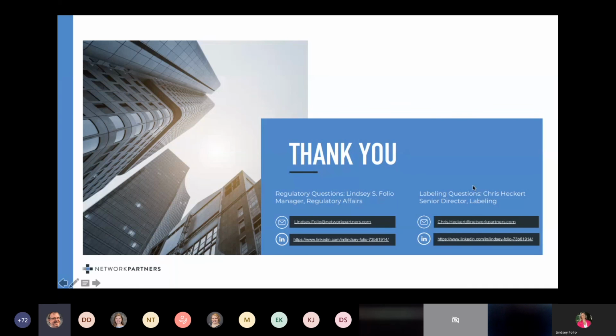You're probably going to have that symbols glossary in your IFU anyway, unless you're using all harmonized symbology. So I'm having a hard time with the question because the symbology is for EU. We put it on the label and we have the opportunity to leverage it with the FDA. I would say symbols glossary in your IFU is the way to go. And you're obviously going to have to put the English definition for those symbols. If that doesn't answer your question, please come back and define it a little better.